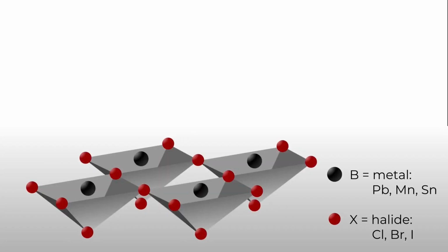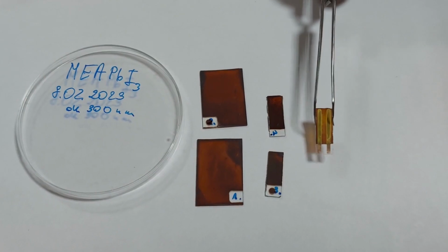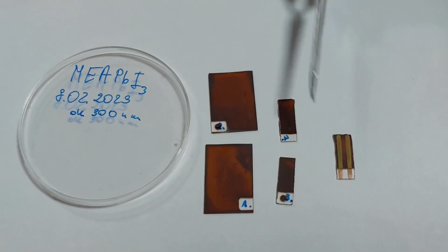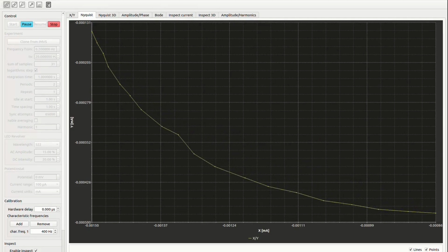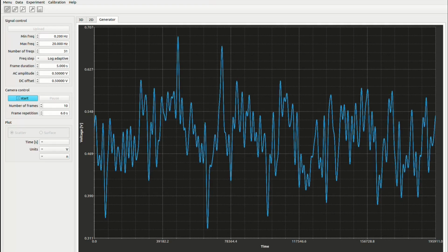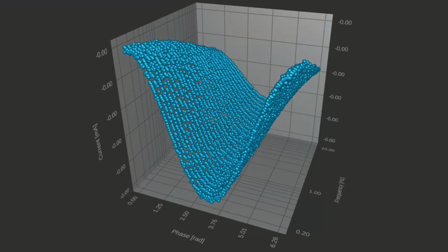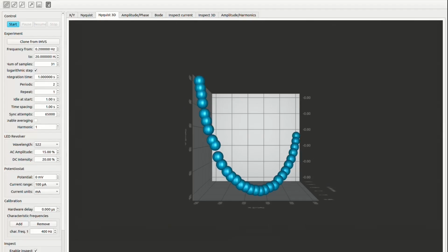Some samples, like perovskites, are unstable. Their properties change during the frequency sweep. So, the beginning of the sweep probes a slightly different sample than its end. In our IMPS/IMVs, we have a solution to that difficulty. The instrument can apply all frequencies of interest at the same time. This achieves two goals: shortens the measurement time and makes the acquired spectra self-consistent.